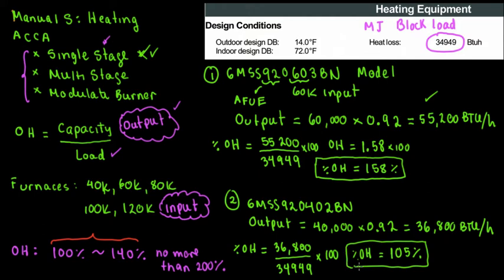That's why it's very important to know which one to put in your house. Based on Manual S and Manual J, you have option one, which is this. Would you put a 60K furnace to your house based on this block load, or would you put a 40K furnace? The answer is, it depends on the designer. Actually, this is an executive decision. If it was my house, personally, I would rather be safe than sorry.